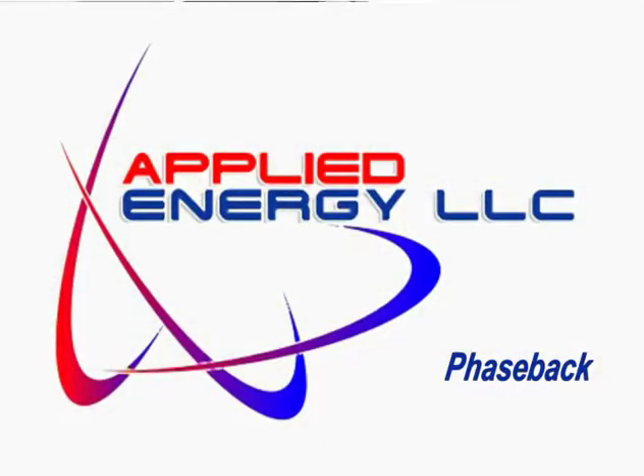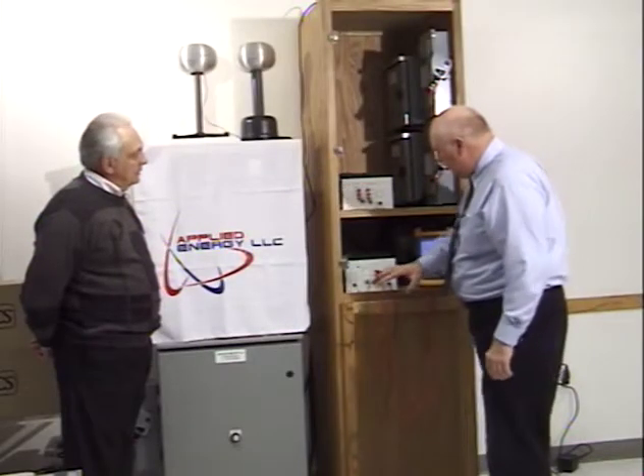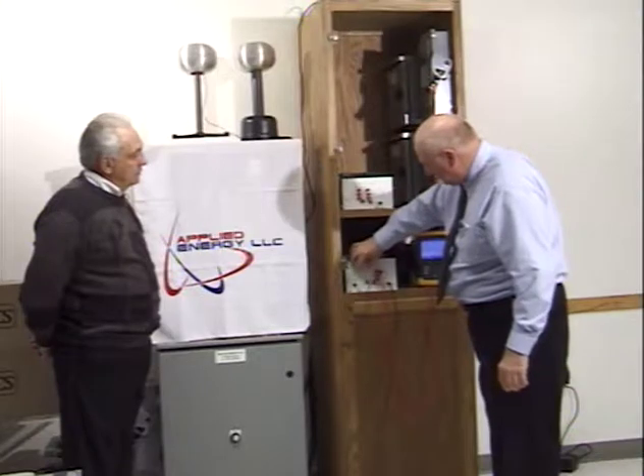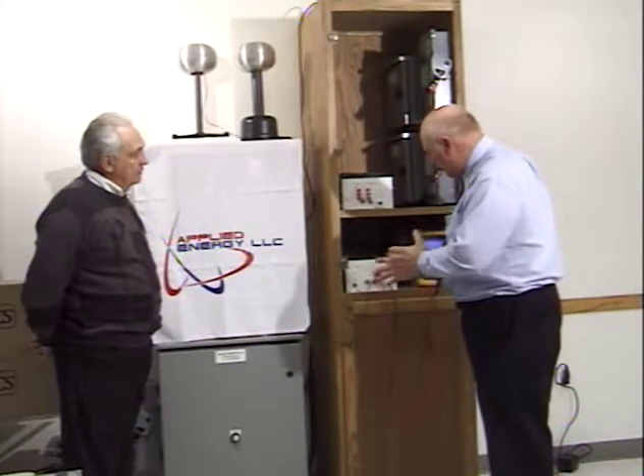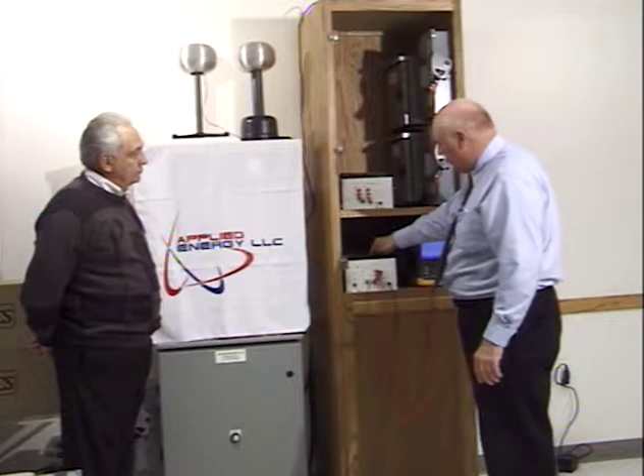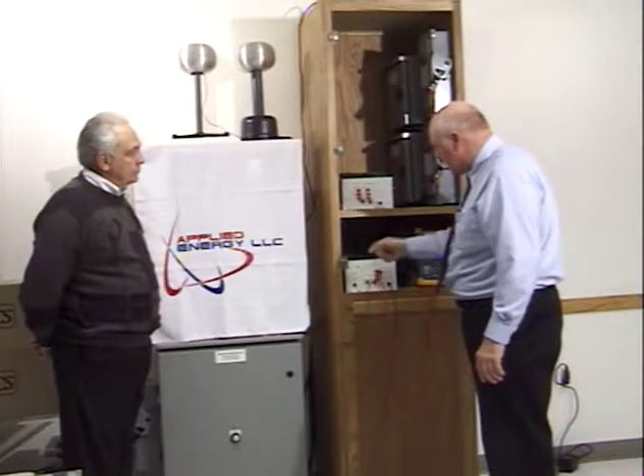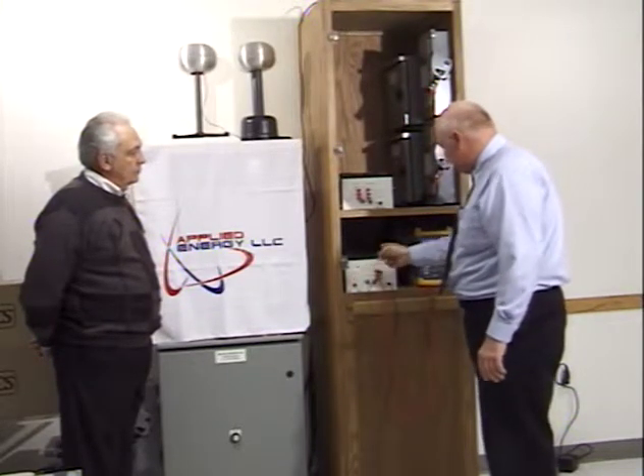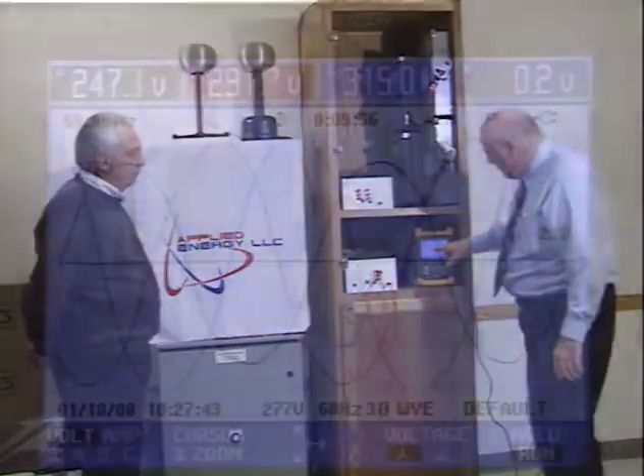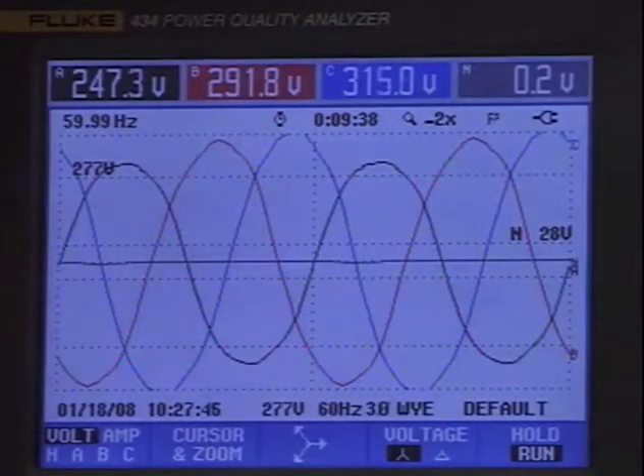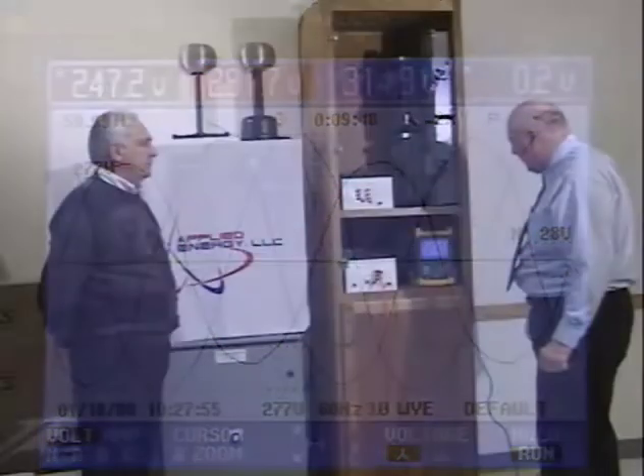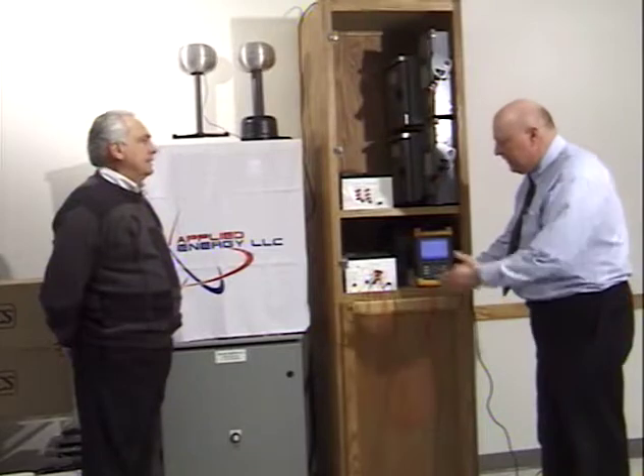Thank you, Dan. The first product we're going to be demoing this morning is Phaseback. What we have at this point is simply the power coming from the building, feeding an across-the-line starter, running this motor. I have a control to turn this motor on. We're showing the three-phase voltages here, and we're showing voltages to ground of 315, 291, and 248. Dan, if you'll turn that on.